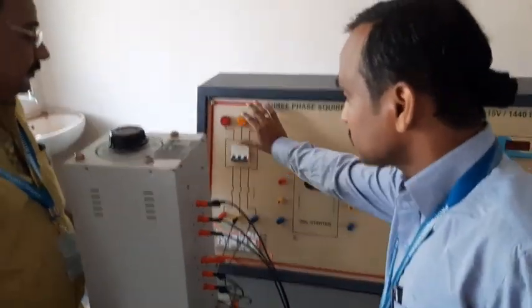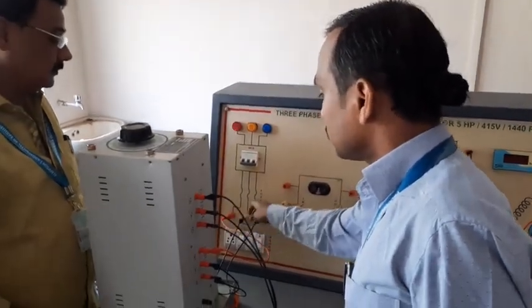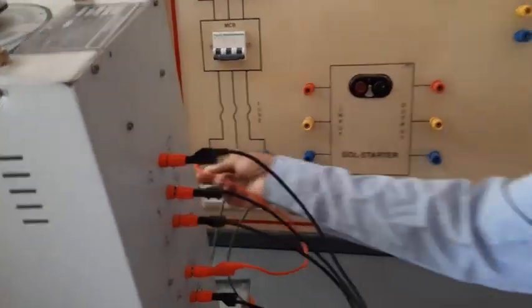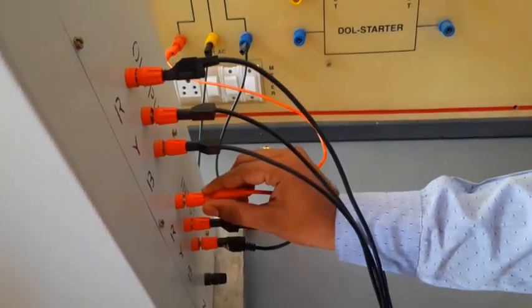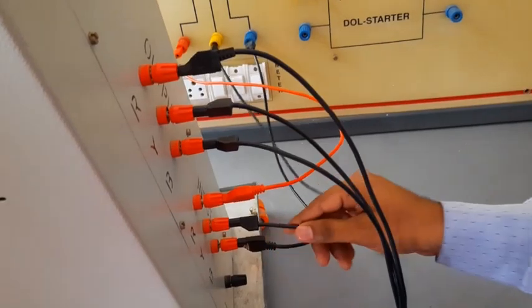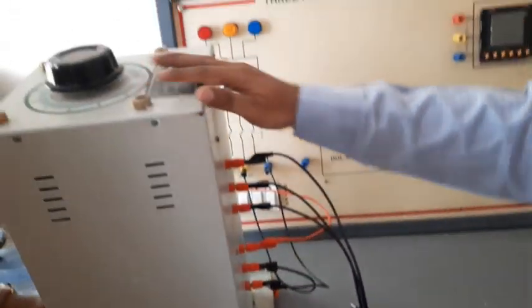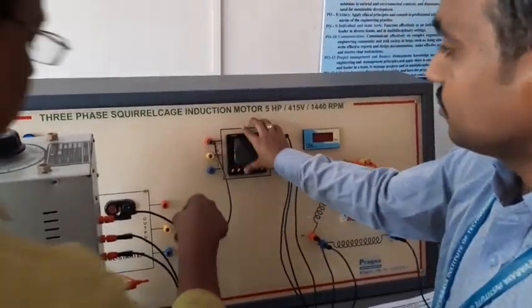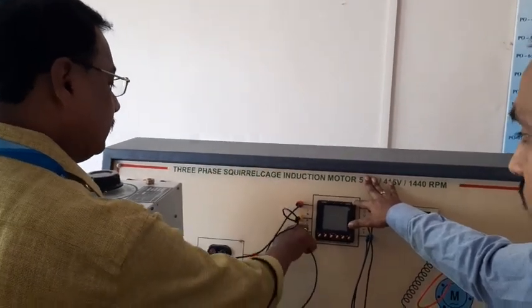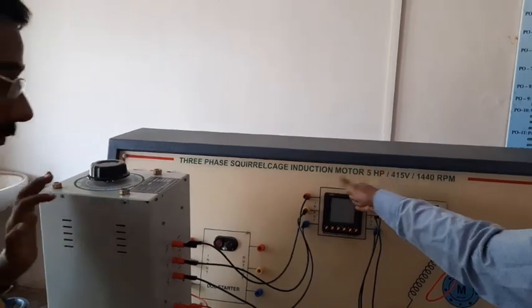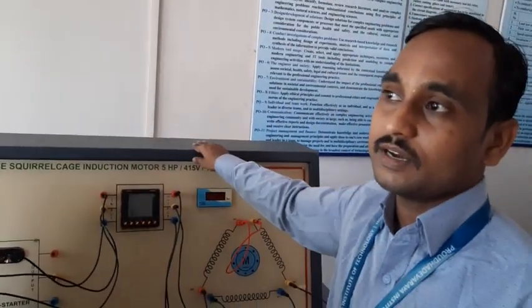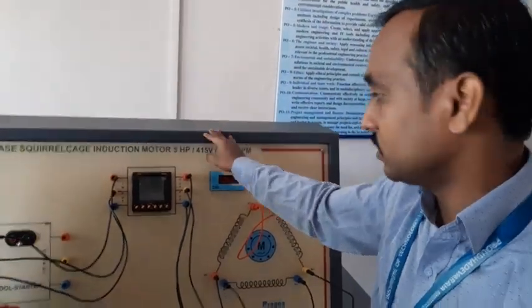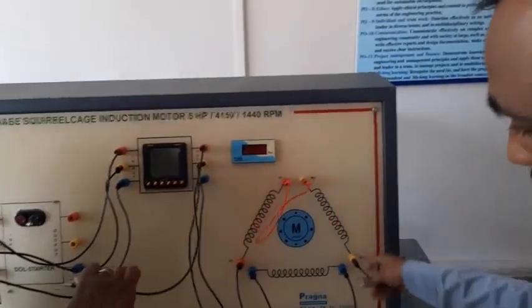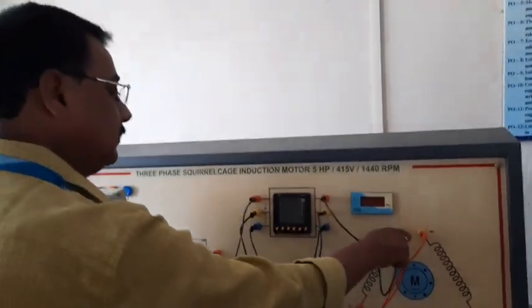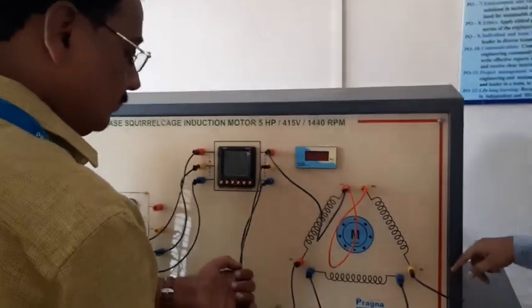Okay. So we have a 3-phase supply. It will come to the MCB from the fuses. Then it will come to the terminals of the motor. For that, on these terminals, R phase is connected to the input of the auto transformer R phase. Y phase is also connected to the input of the auto transformer Y phase and B phase, and the output of the auto transformer is going to be connected to the meter. This is the multifunction meter. We can use it for voltage measurement, current measurement, power measurement and power factor measurement, etc. If you do not have a multifunction meter, use analog meters, connect the 2 wattmeter method, and calculate the total power. Okay, so now this is the delta connected motor, connected in series. Now connect R phase to R phase, Y phase to Y phase, and B phase to B phase.